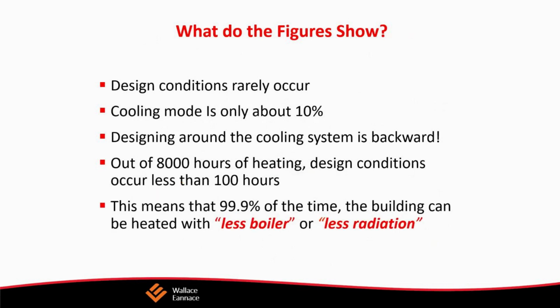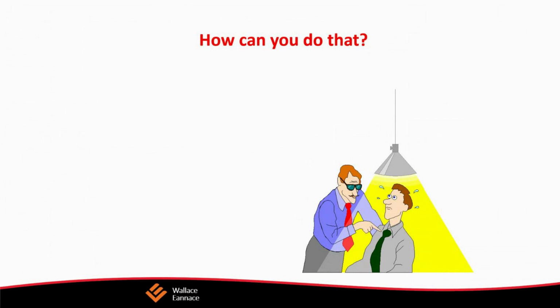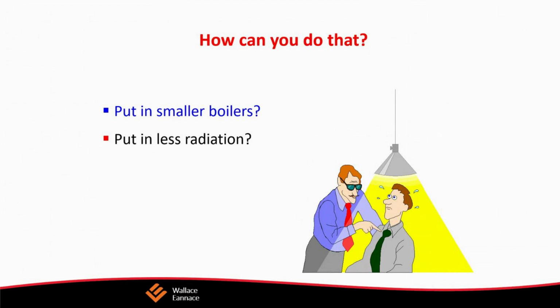But when we were evaluating that system, we had to look at the building and consider what was happening. And we had to think about heat loss. So what is heat loss? Because that's what we're providing heat to a space for, and really we're looking to compensate for the amount of heat that's being lost. It's the rate at which heat leaves the building. And it also depends on the conditions. And from that information, that's how we size boilers, and that's also how we size radiation.